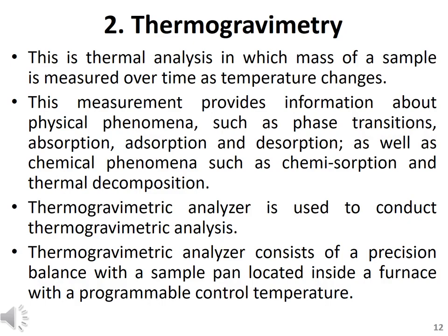Different pressures can also be employed in TGA, such as high vacuum, high pressure, constant pressure, or controlled pressure. The thermogravimetric data collected from the thermal reaction is compiled and plotted by taking mass on the y-axis and temperature or time on the x-axis, producing a thermogravimetric analysis curve. This TGA curve can be used for material characterization through analysis of characteristic decomposition patterns.